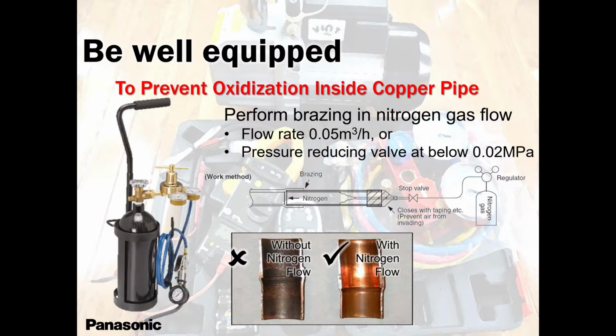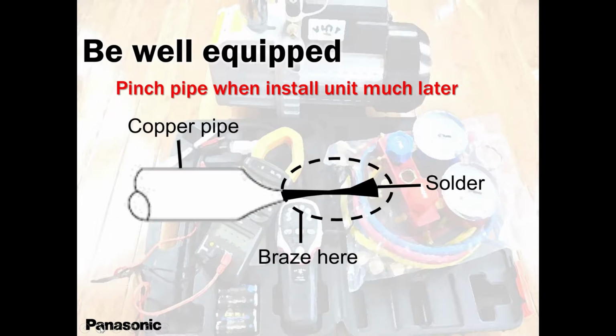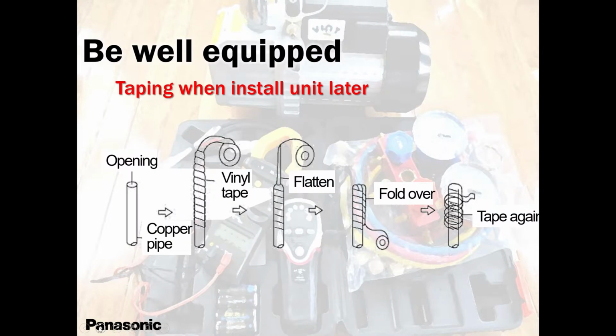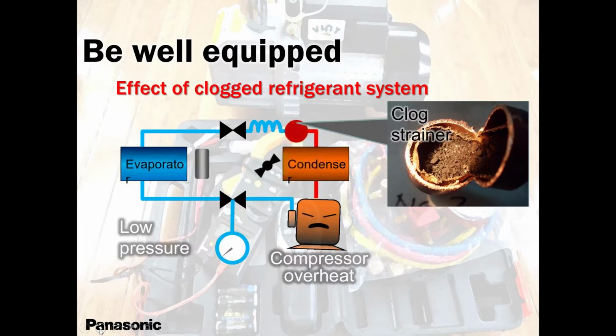And we have almost 4 meshes at the outdoor unit, and about three meshes at the indoor unit. And they are very fine, easy to attract that. Another problem is the leak lock. I'll talk about this later because I have some pictures regarding leak lock. Leak lock also is not allowed. But when you go to a refrigeration store, they are selling it and people are buying because refrigeration equipment, cold storage, mortuaries, and those kinds of things, which I work on as well, don't have those meshes that I was talking about in heat pumps. So leak lock can be good for other stuff, but not good for our stuff. Please do not use it. I had problems with it. This is what happens. Everything is clogged. Compressor is complaining.